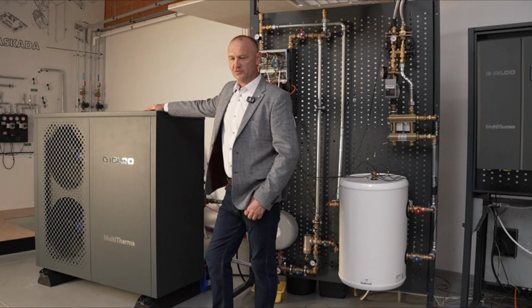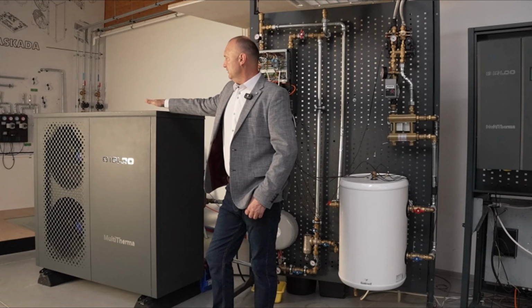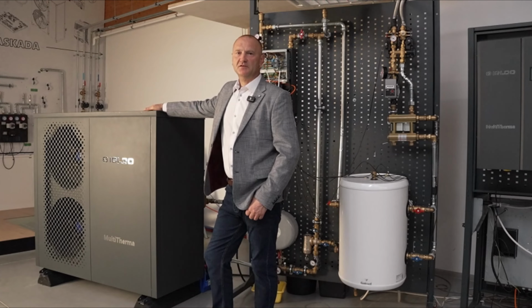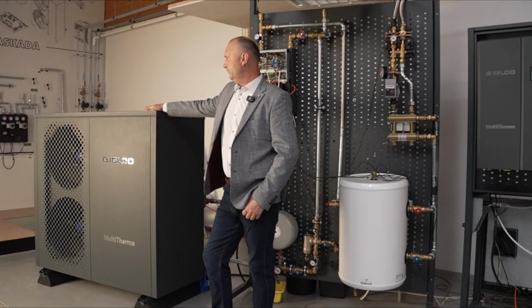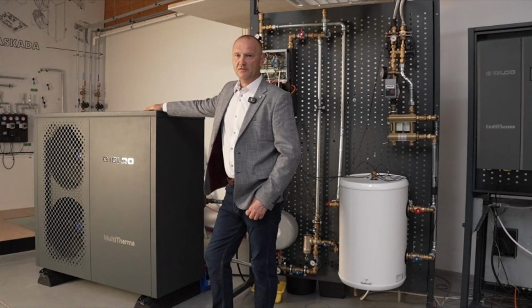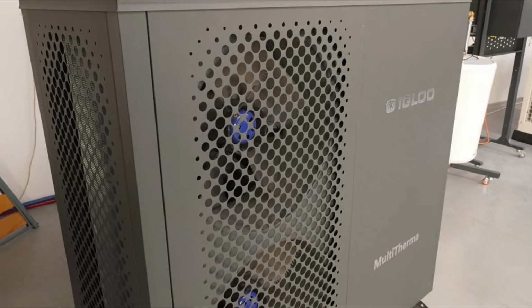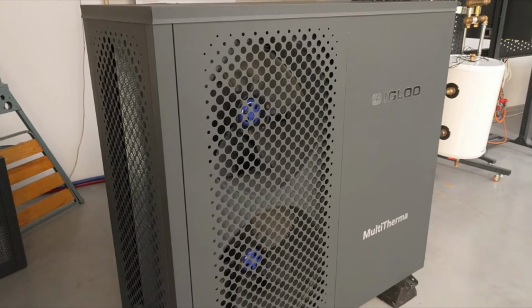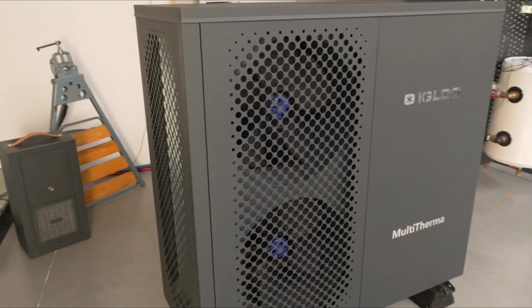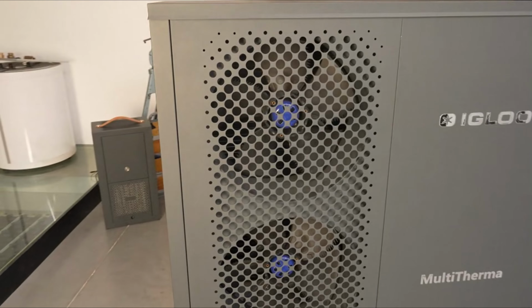Currently, we offer three sizes of devices, a 12, 17, and 21 kilowatt heat pump. The 12 is a unit that can operate in a range from 1.27 to 12 kilowatts, the 17 from about 2 to 17 kilowatts, and the 21 from 2.4 to 21 kilowatts. These are devices with a very wide modulation range. They are capable of modulating their performance within a range from 10% up to 100%.